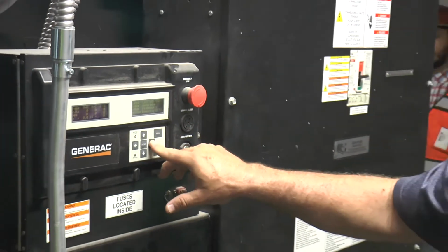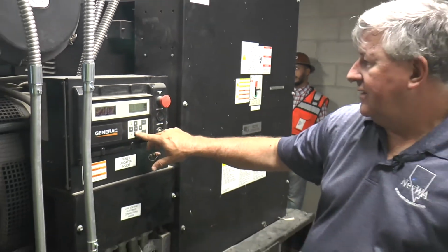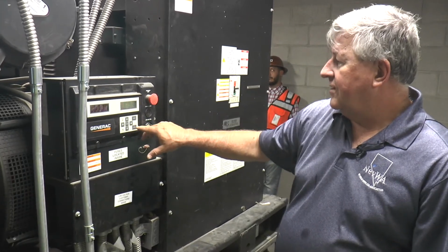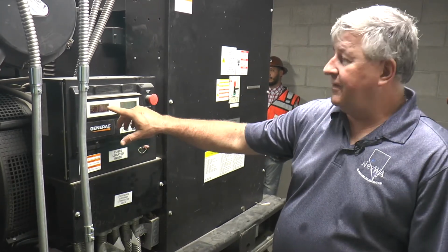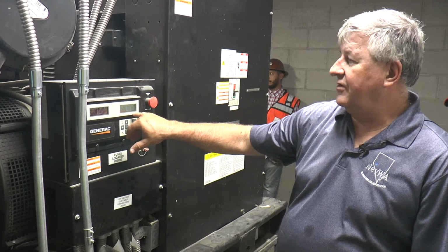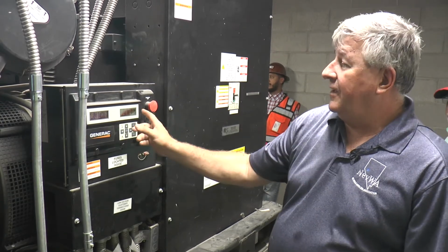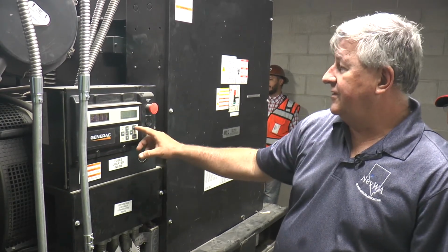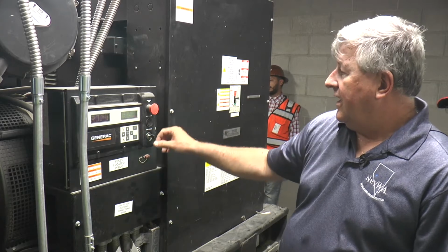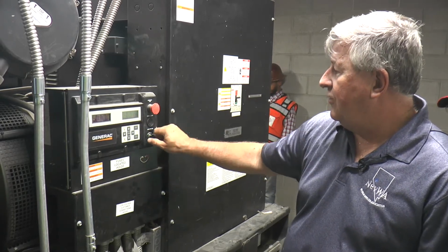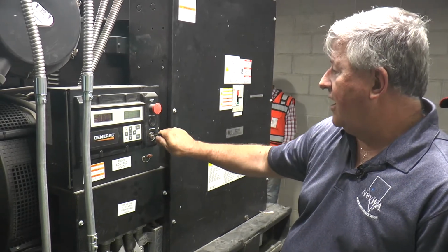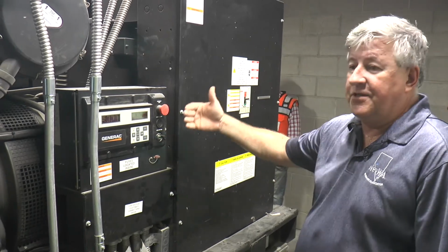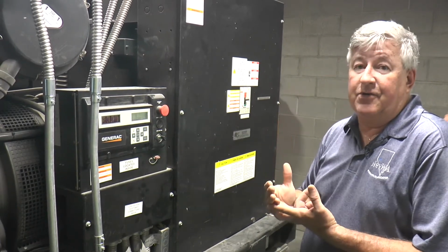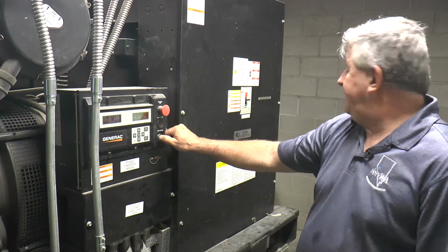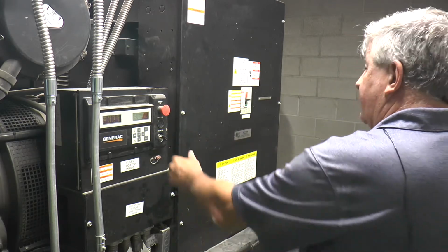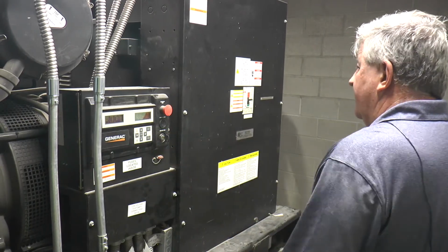Menu screen again, we'll go over to generator, which is going to basically pick up the same display that's on the left-hand side, showing it on the right. And the ability to interchange those if you need to. Controls, you have a key for auto. Auto in the auto start position, generator can start at any time during a power outage. If you're here, someone's working on the equipment, put the key to off.